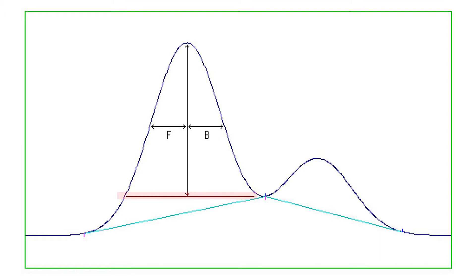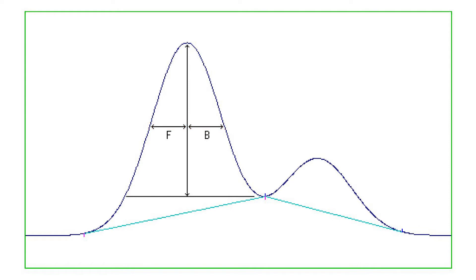First, an auxiliary horizontal baseline is drawn from the baseline start or end point, whichever is higher. A second horizontal line is positioned halfway between the auxiliary baseline and the top of the peak, measured along the vertical line through the peak top.